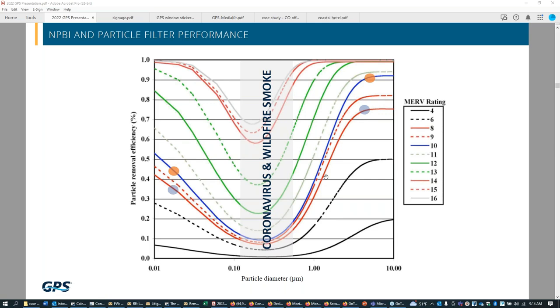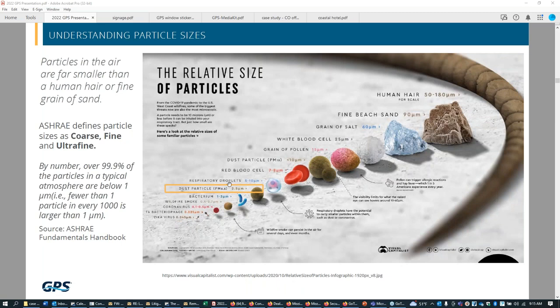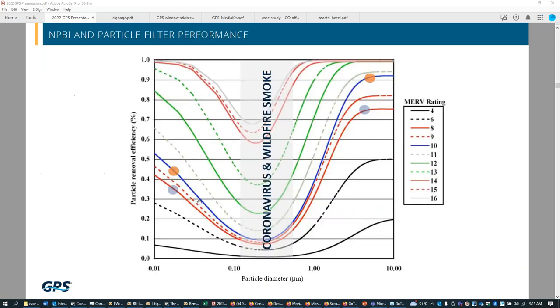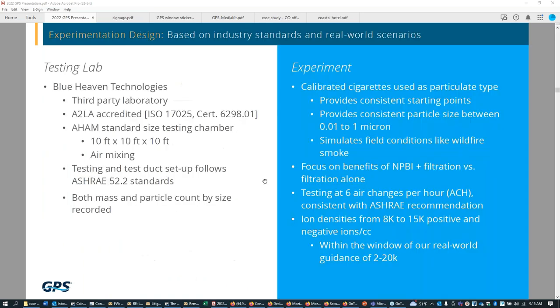But it intuitively makes sense that larger particle sizes should have higher removal efficiencies for every filter. And they do. As we get beyond one micron, all of the filters start to get above 50%. They start to do really well. But down here in this 0.3 to 0.4 range, which is where some dusts, viruses, and wildfire smoke reside, all these filters have this weakness.